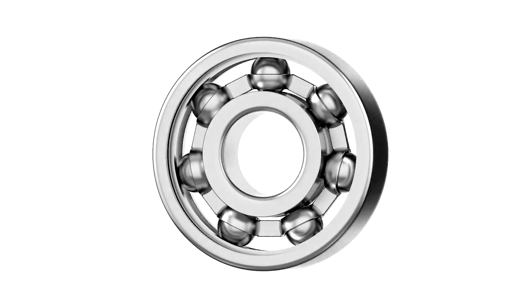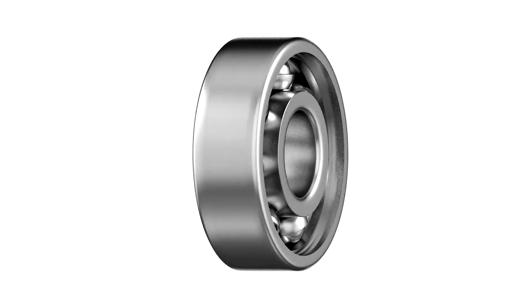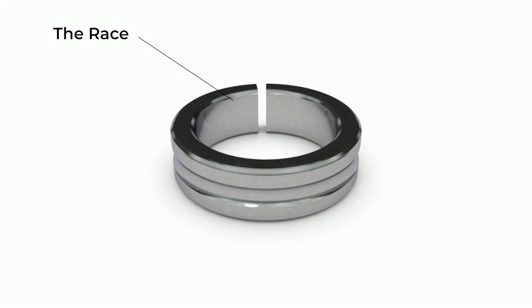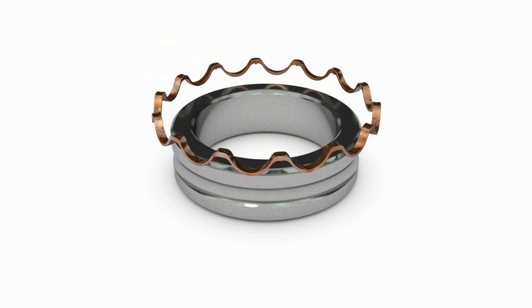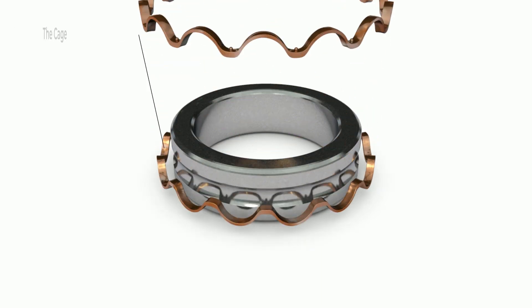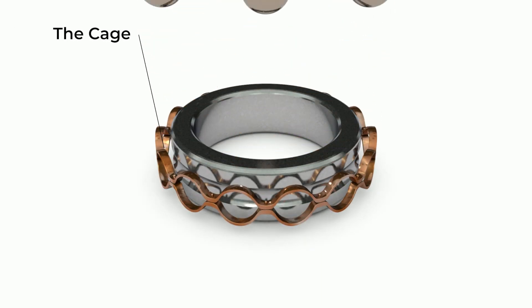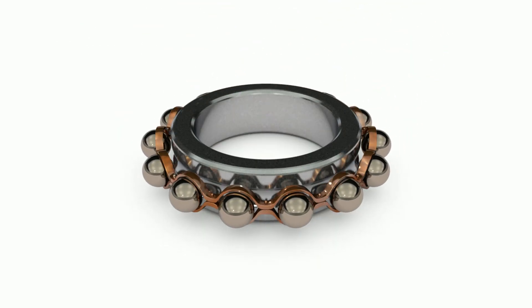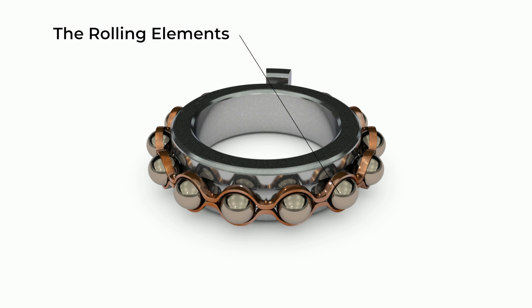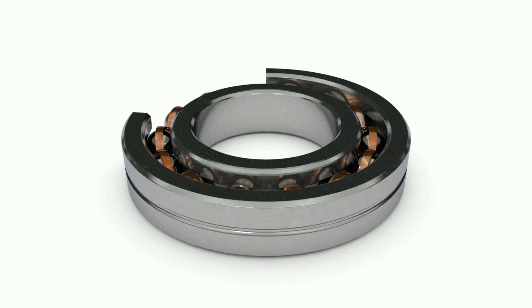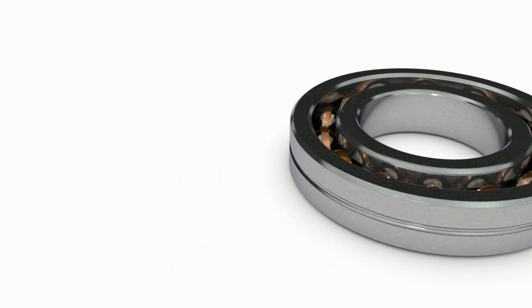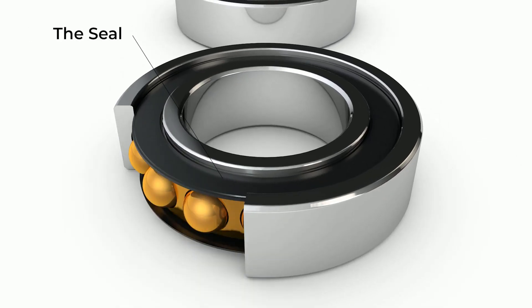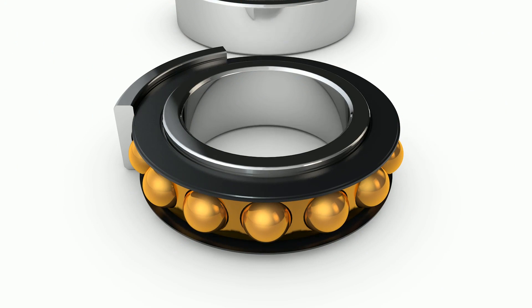Bearing malfunctions are the leading cause of motor failure. The bearing structure includes four key elements. First, the race — most motor applications have the inner race rotating and the outer race fixed. Then there's the cage, which keeps the rolling elements separate so they don't collide while still allowing them to rotate freely. Third, rolling elements — typically balls or cylinders are the rolling elements used in the bearing structure. Finally, the seal, which offers protection against outside debris and helps keep the grease inside the bearing.